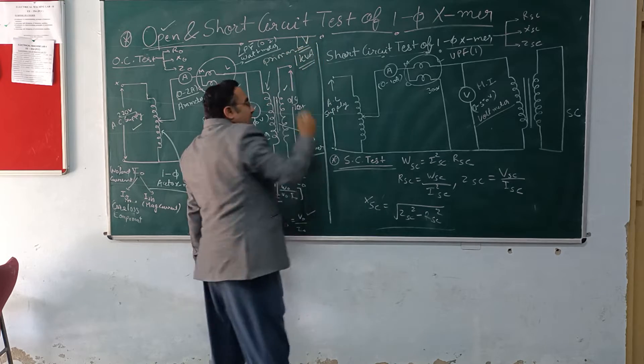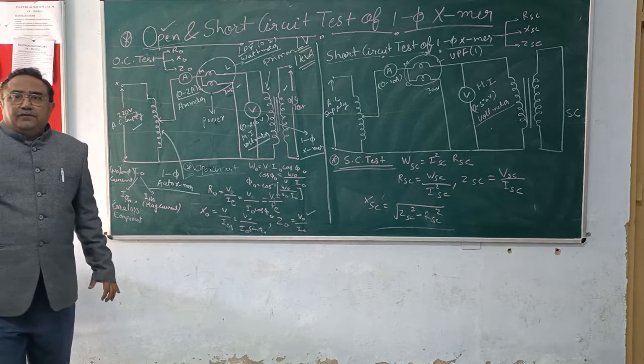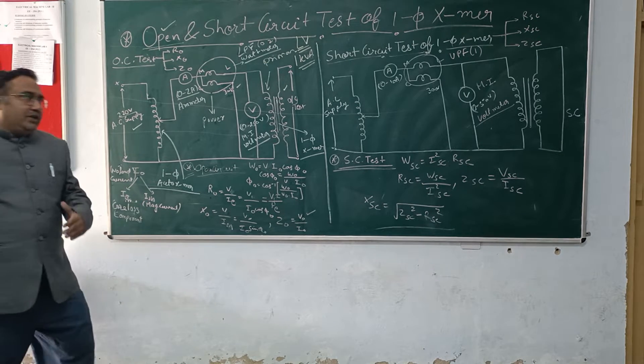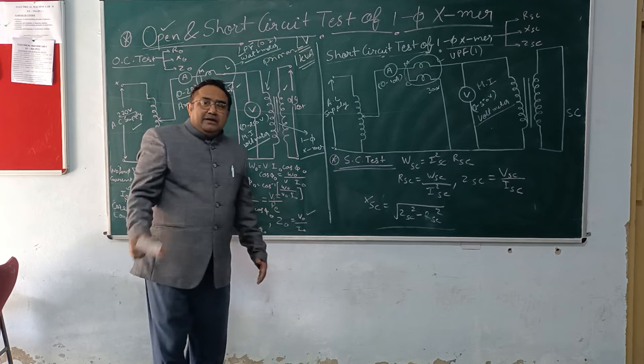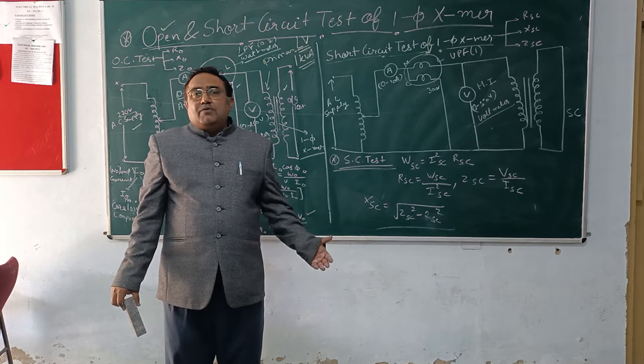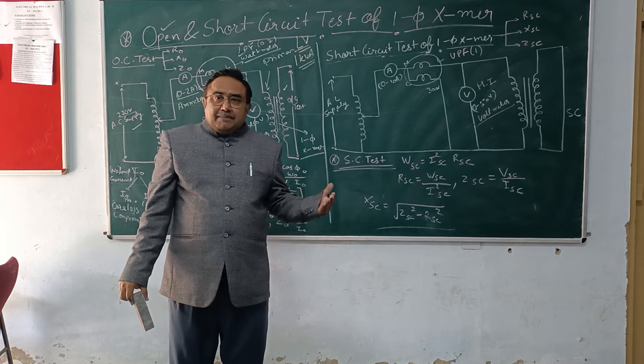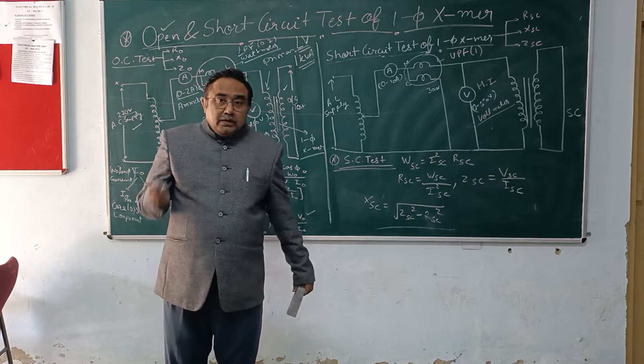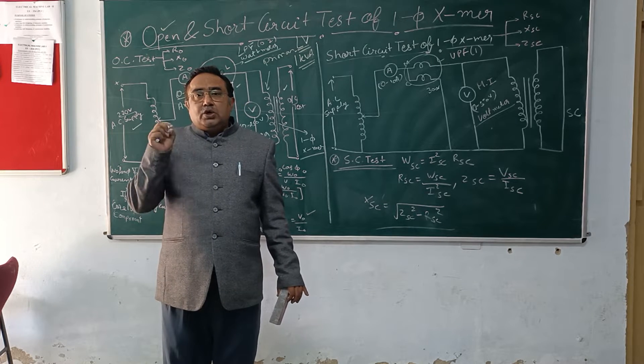Here we have a transformer of turn ratio 1:1 - that is, the number of turns on the primary and number of turns on the secondary are the same. But in general, when you go to the practical field, you will find the primary side is the low voltage side and secondary side is the high voltage side, or vice versa. In that case, the open circuit test is always performed on the low voltage side.